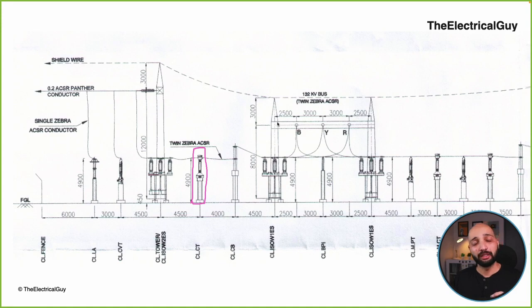Now if you want to measure that current, then you will have to build very big meters, very big relays for protection purposes, and that is again not the right way, not the smart way to do it. And hence what we are doing is stepping down that current and then measuring it and using it for protection purposes, and that's when the current transformer comes into the picture.